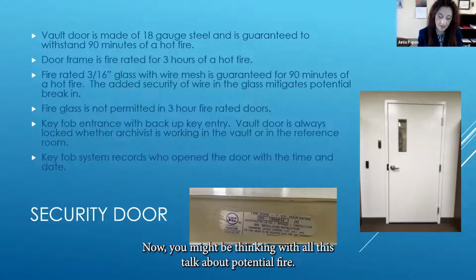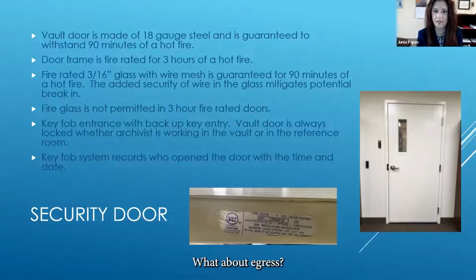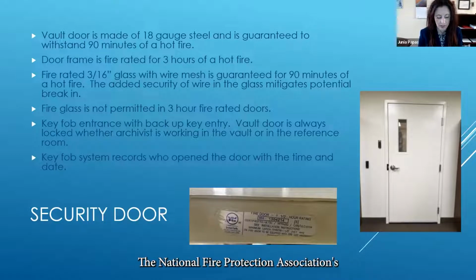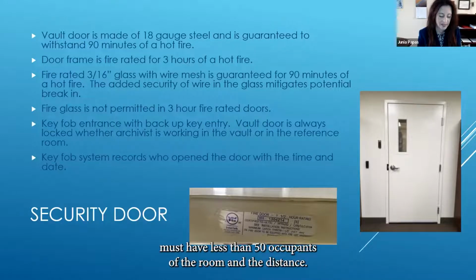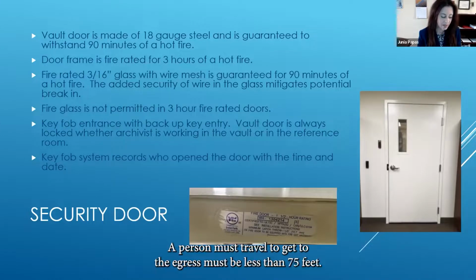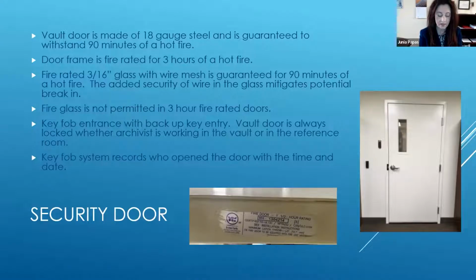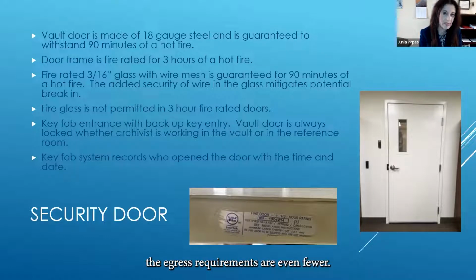Now, you might be thinking, with all this talk about potential fire, what about egress? The National Fire Protection Association's fire code for a room with one exit says the room must have fewer than 50 occupants, and the distance a person must travel to get to the egress must be less than 75 feet. Also, in an automatic sprinklered room, the egress requirements are even fewer. The dimensions of our archival vault are well within these parameters.